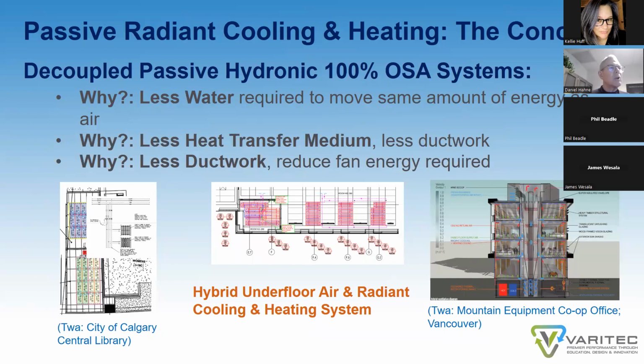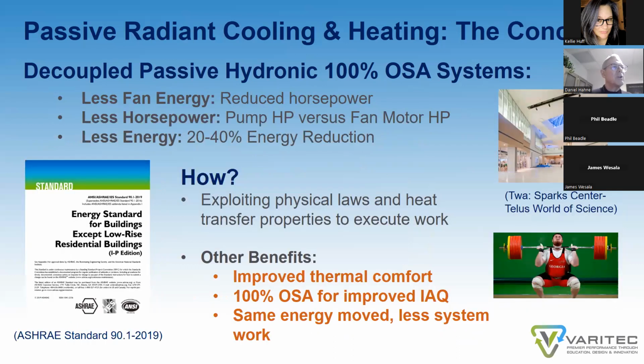Well, less water would be required to move the same amount of sensible energy from the building. Why? Well, less heat transfer medium means that using water as opposed to air would mean less ductwork. Less ductwork results in reduced fan energy required to condition a building. Less fan energy results in reduced horsepower. Less horsepower, pumping horsepower versus fan horsepower, and consequently buildings historically that apply passive 100% outside air systems are seeing 20 to 40% energy reduction.